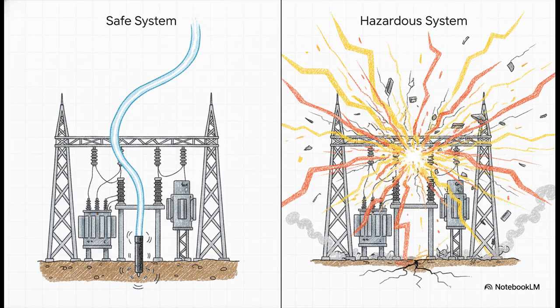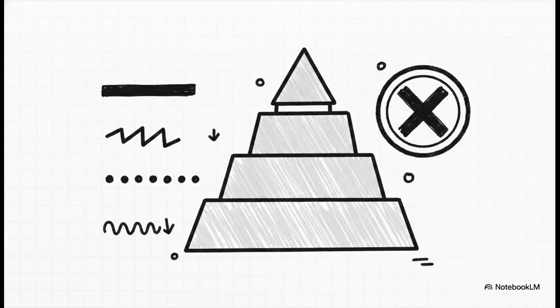We're talking about the defining physical factor that decides if a massive electrical fault clears safely or if it literally destroys a substation and turns into a deadly hazard. It is absolutely the primary lever we have for controlling fault current. So here is the overarching rule you've got to memorize for the grid. The system is split into 4 voltage tiers, and every single one of those tiers tackles the physics of grounding in a completely different way. 4 tiers, 4 totally distinct earthing philosophies. You absolutely cannot just guess or try to force a one-size-fits-all approach here.